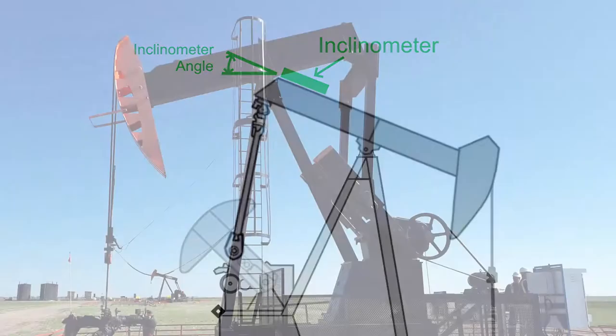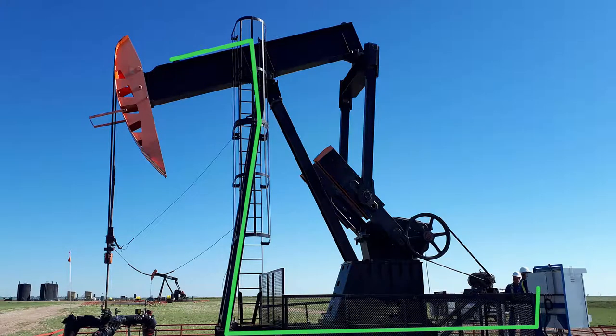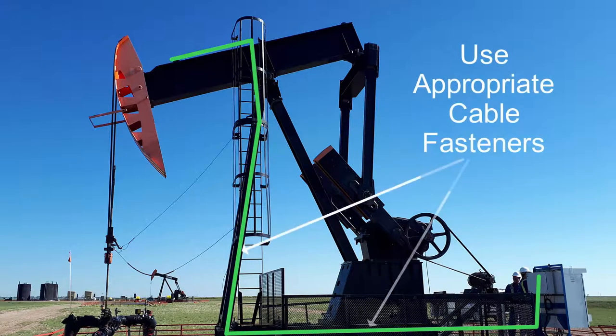When the inclinometer is installed on the walking beam, run the sensor cable from the inclinometer to the panel or enclosure containing the Reallift RPC. Route the cable such that the cable will not be able to snag, catch, or pinch on moving equipment. Secure the cable to the pump jack frame using eye bolts, U-bolts, outdoor rated cable ties, or other similar fasteners.